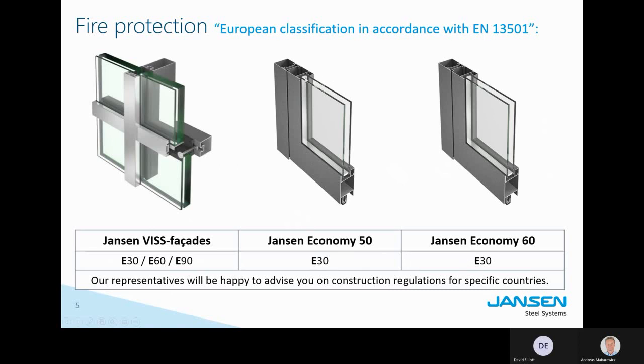What you also see on this cross section of the profile is that there is no thermal break and no cooling element in the profile. It's basically a pipe, a tube. So it will let the radiation pass through. That's class E. It's the cheapest fire protection class, and it's used for sections of the building where you just quickly get out of your compartment, and you're out. That's it.